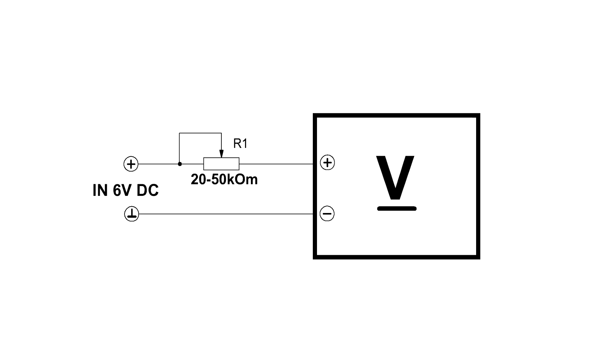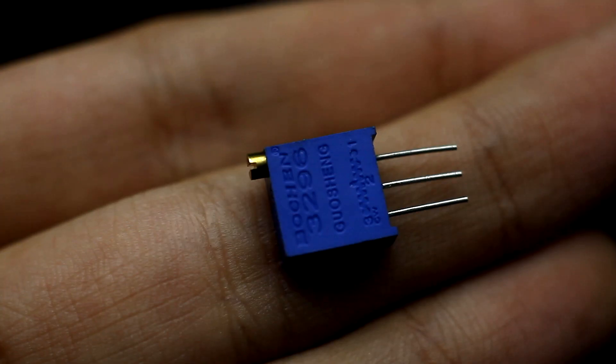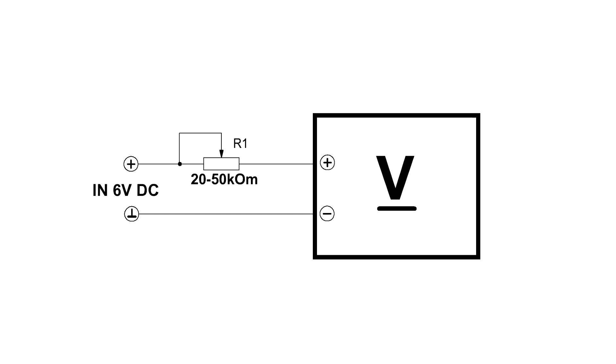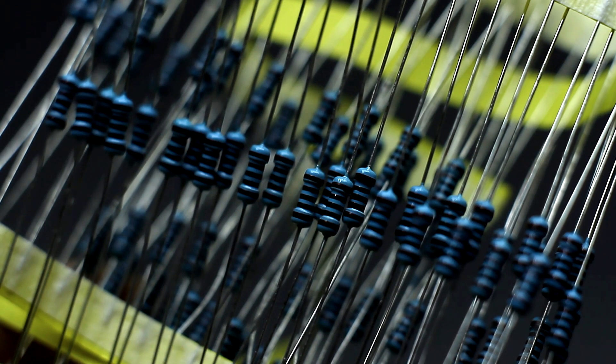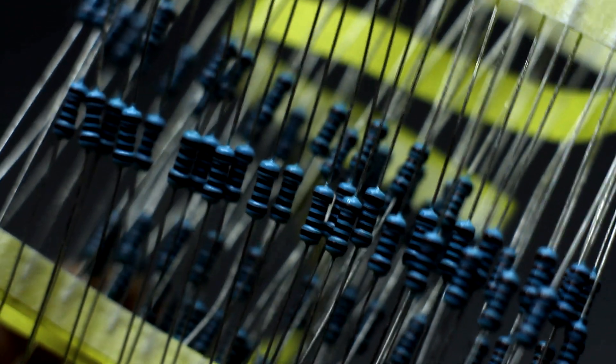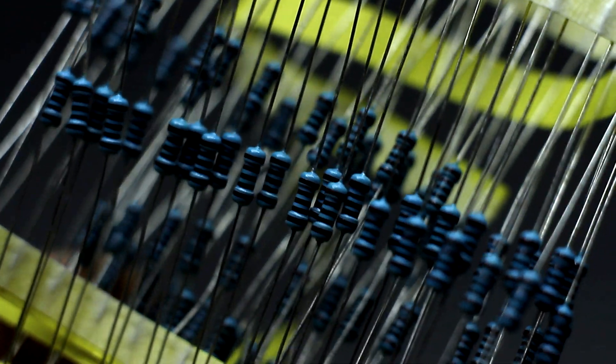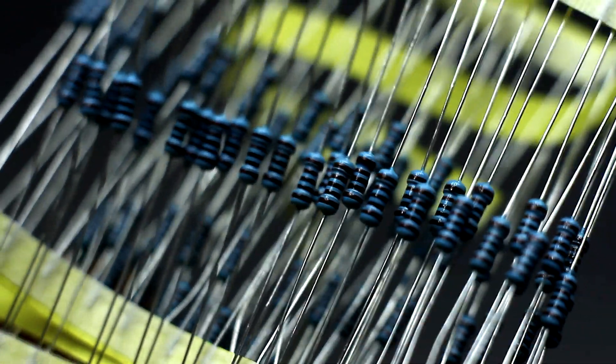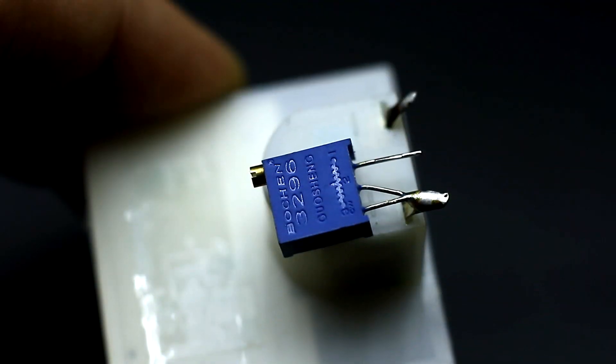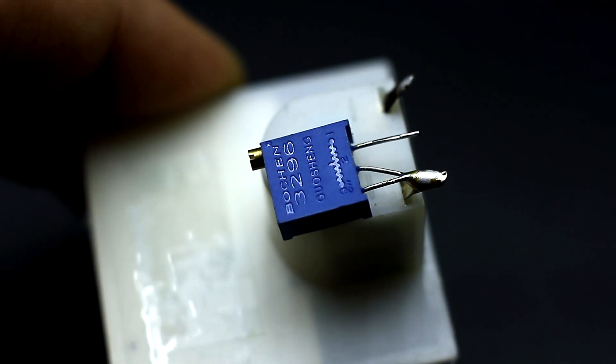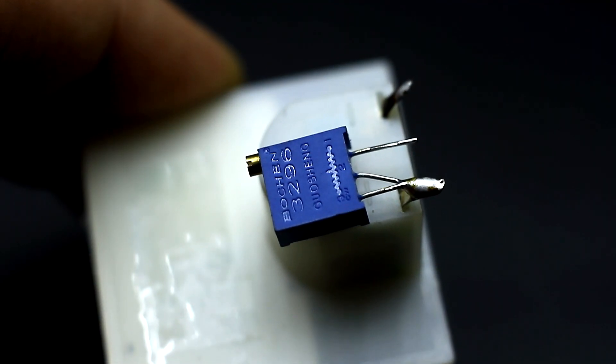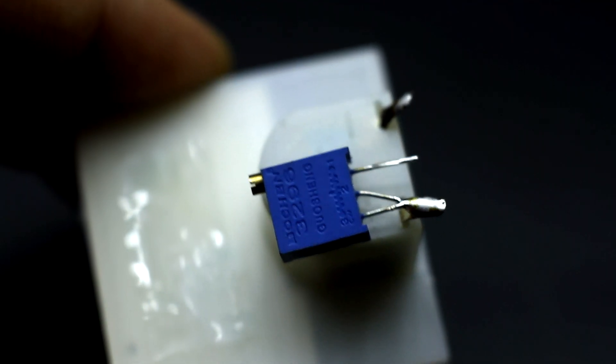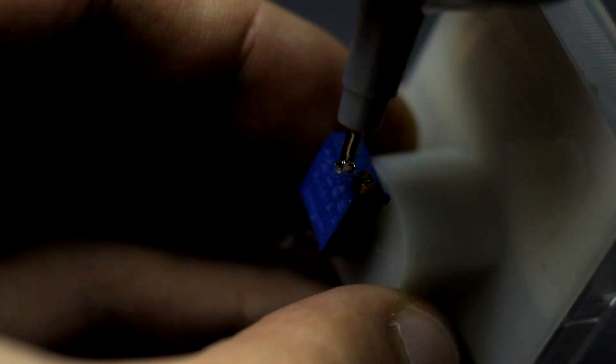After calibration, the trimming resistor is removed. The obtained resistance is measured and replaced with a constant resistor of the same resistance. If there is no desired nominal of resistor, then several resistors can be connected in series to obtain the desired value. It is desirable to use resistors with an accuracy of 1% and less. Also, a trimmer can remain, but you must fix the adjusting screw with glue to prevent further displacement.